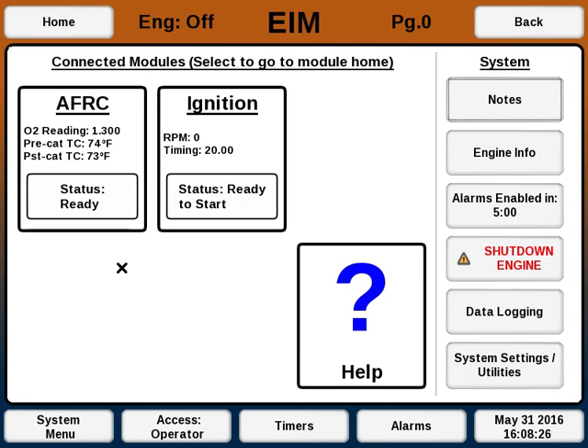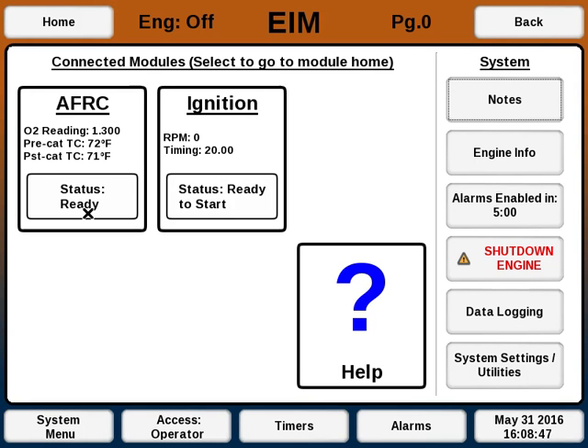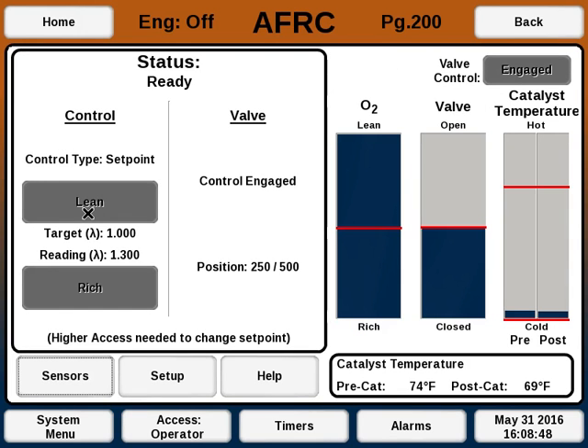On the home screen, it will show a button for every module that is attached and detected. If the module does not show up, verify that it's wired properly, that the CAN termination switches are in the correct direction as listed in the installation guide, and that it's properly powered on and the light is showing green. Once it shows up, you can select it and go to the home screen for that system.